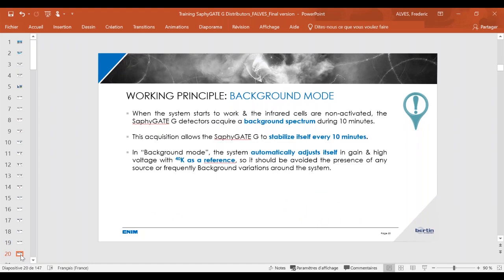Concerning the background mode, when the system starts to work, the infrared cells are non-activated, for sure, and the SaphyGATE G detectors acquire the background spectrum during 10 minutes. This acquisition allows the system to stabilize itself every 10 minutes. Very important to keep it in your minds.